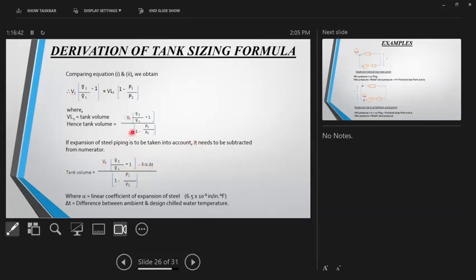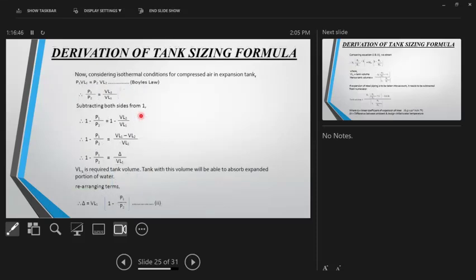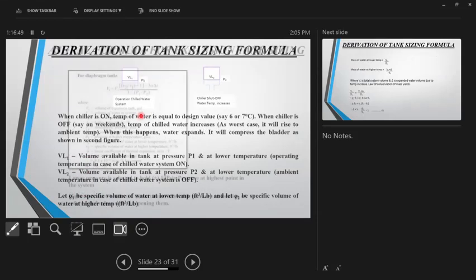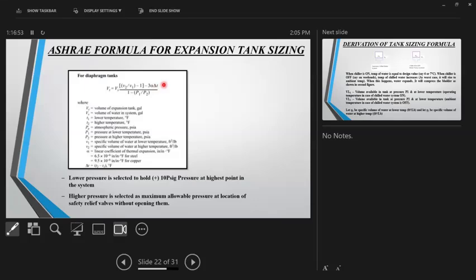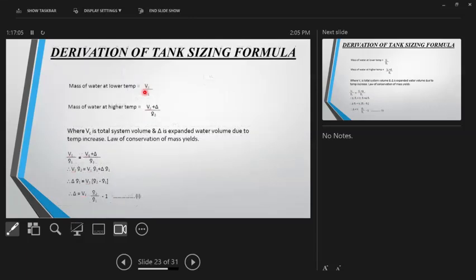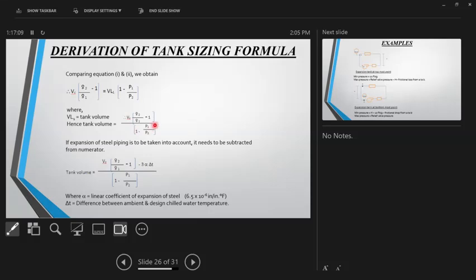So now you see this equation, I will go back, was the same as what we saw here, except this term, because for the derivation we didn't worry much about the piping. So if you neglect this term, this side of the equation is exactly the same as what we derived. And this term is added to take advantage of the steel expansion volume also, so that you can optimize your tank size, where alpha is the linear coefficient of steel. If it is copper, it is different. For aluminum, it is different. And this delta T is the temperature difference between ambient and desired chill water temperature. So that's how we can see that the equation in ASHRAE looks good and logical.